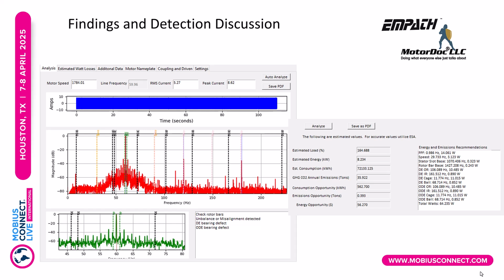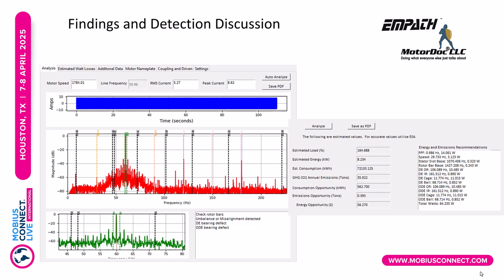Well, smaller machine. And as we go down, we can see the total watts, and you can see over there on the bearings, like 10 watts on DEOR, 10 watts on ODEOR. That means those bearings are basically the same size, right? Nope. So we actually have two different faults going on, and they're about the same value. And then we can also see the cage. So we have the same problem going on with both those machines. And you'll notice that they're in watts.